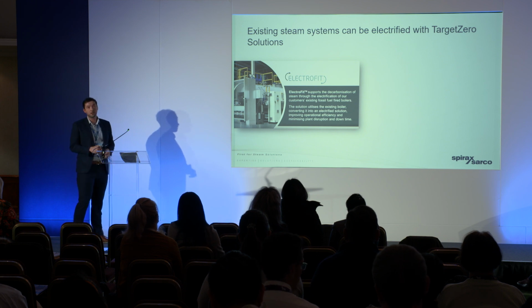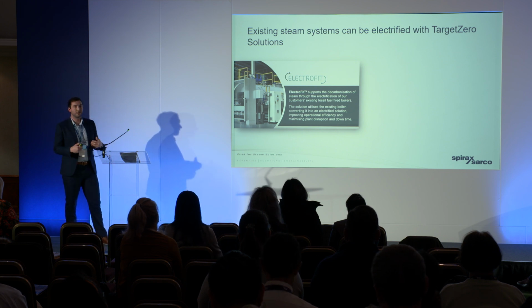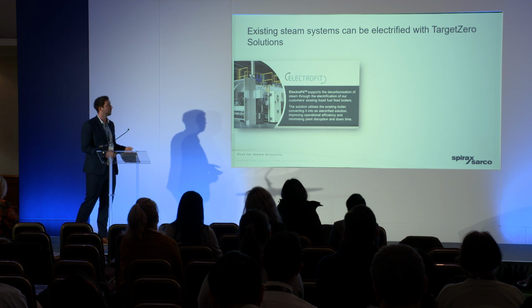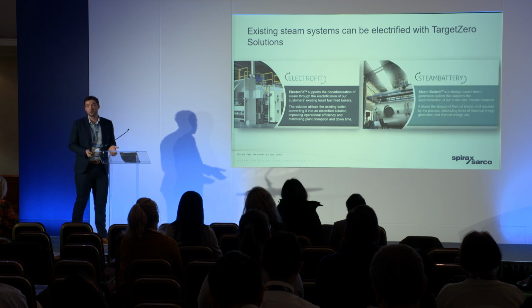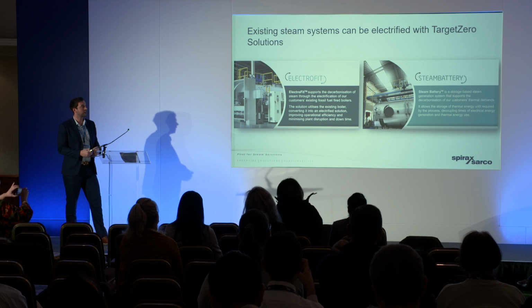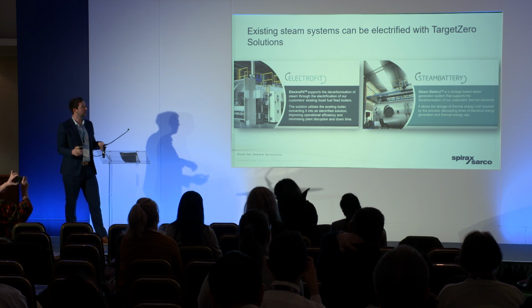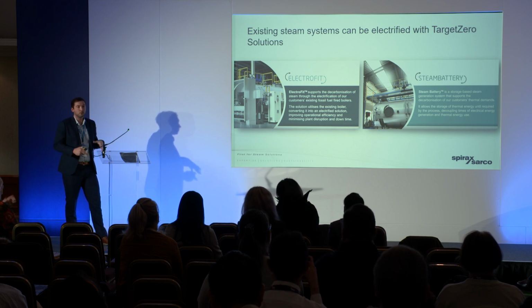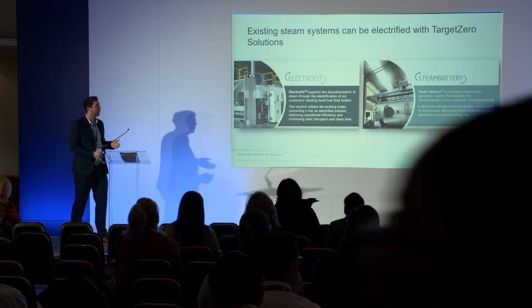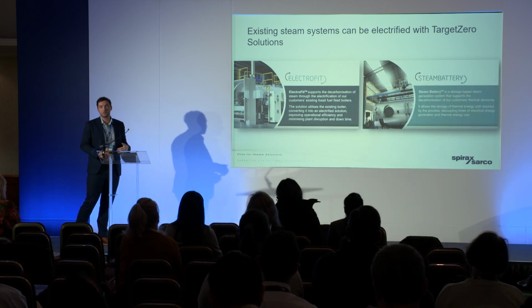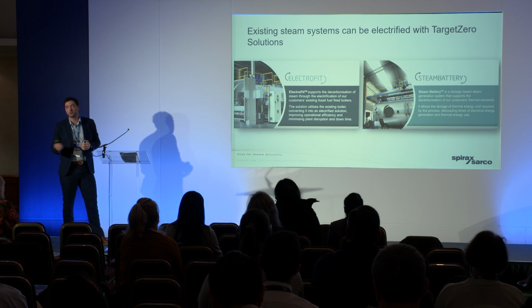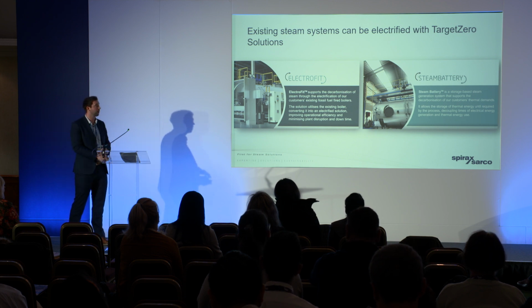The Electrofit I've spoken about very briefly is our technology for electrifying an existing gas boiler. And we've got a storage solution too, called steam battery, which is a high-pressure storage tank. We're using electricity to store steam in the same way you'd use an accumulator and then distribute that when it's needed. It's capable of really high peak flows, really suitable for what Chris was talking about before, and multiple sterilizers coming on at once.